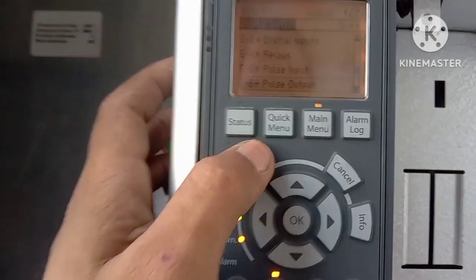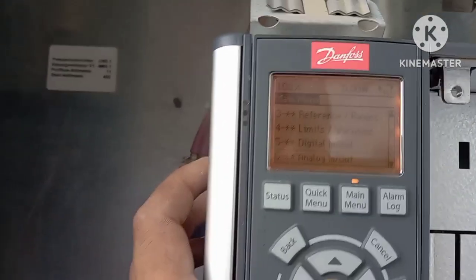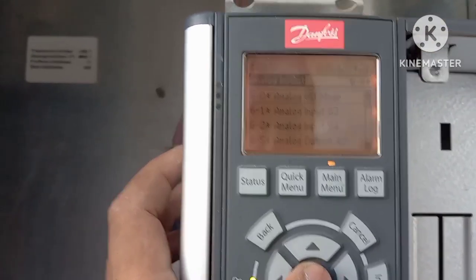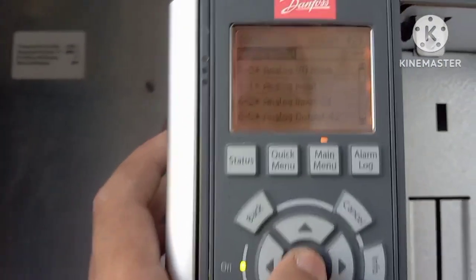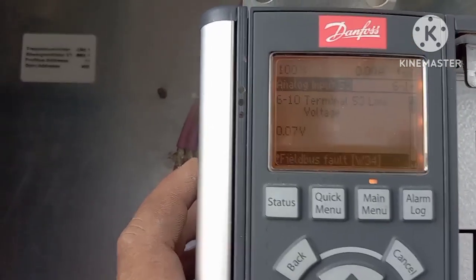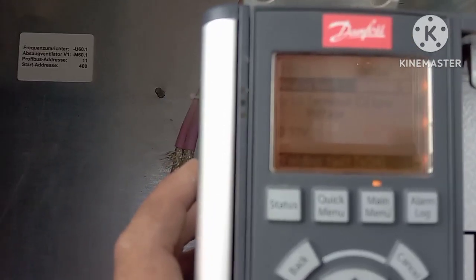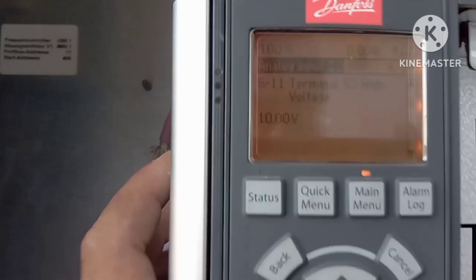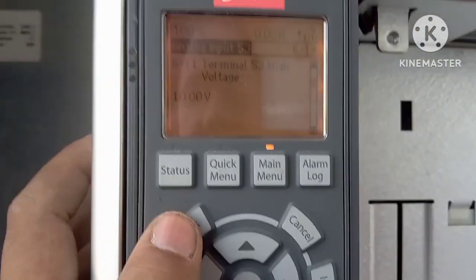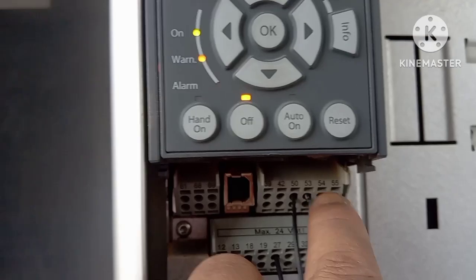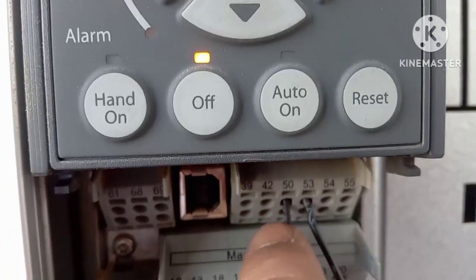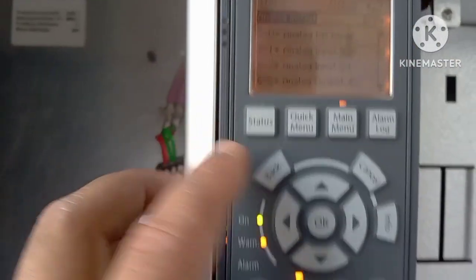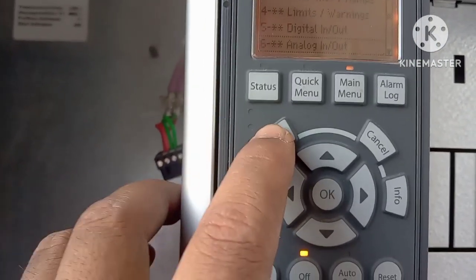One more important parameter — analog input. When you are using a potentiometer or external analog input, you have to set the low voltage and high voltage here. I am using terminal 53 as the analog input signal and terminal 50 as the 10-volt reference. That completes all the important parameters.